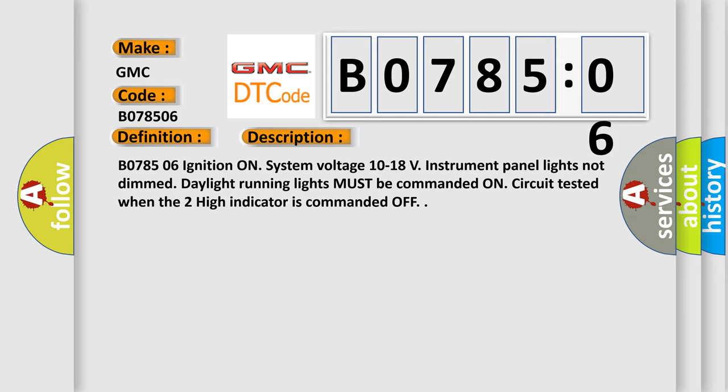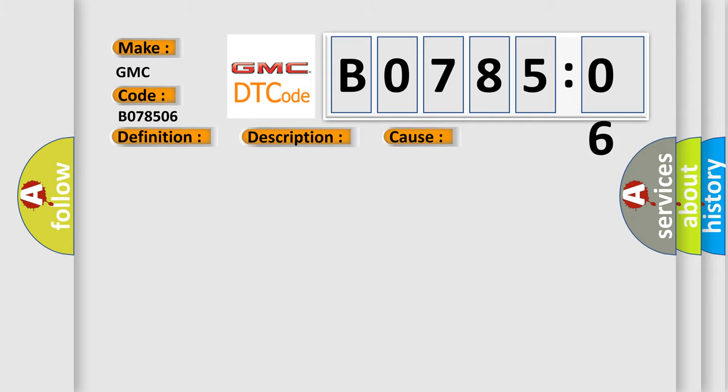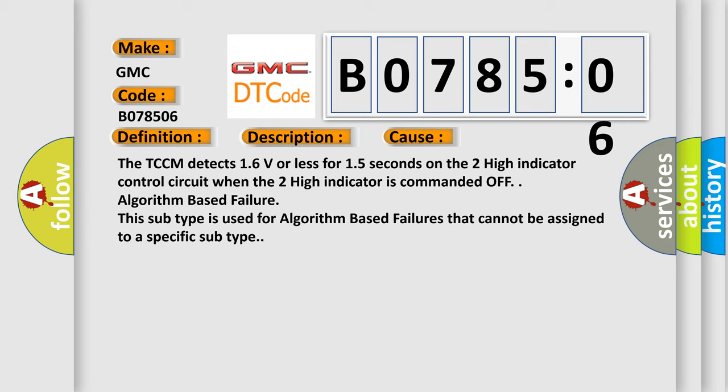This diagnostic error occurs most often in these cases. The TCCM detects 1.6 volts or less for 1.5 seconds on the 2 High indicator control circuit when the 2 High indicator is commanded off.